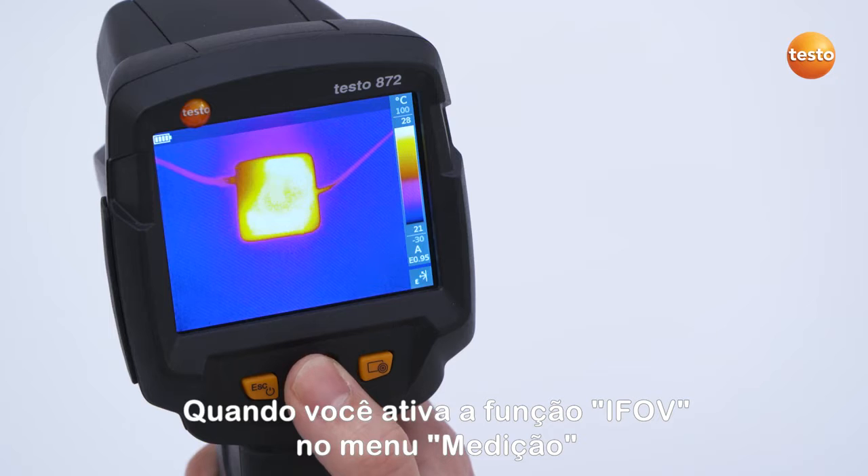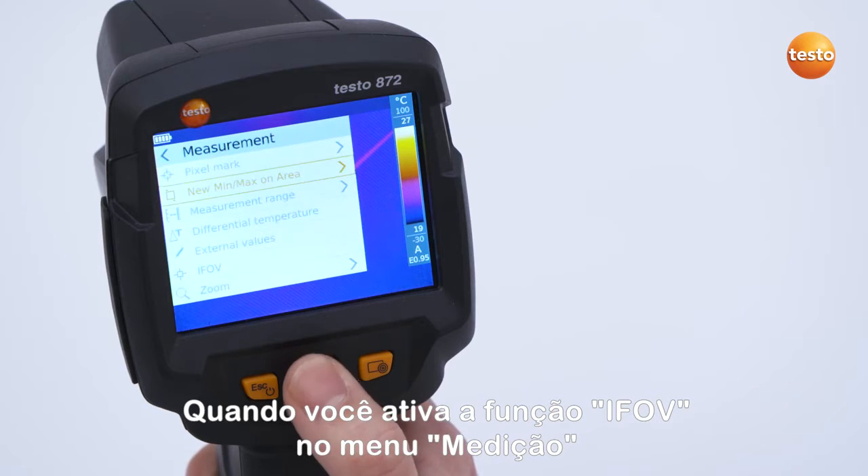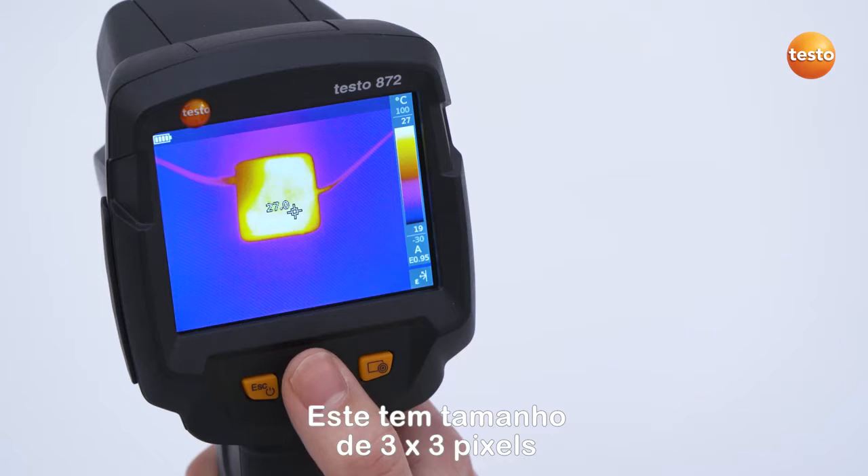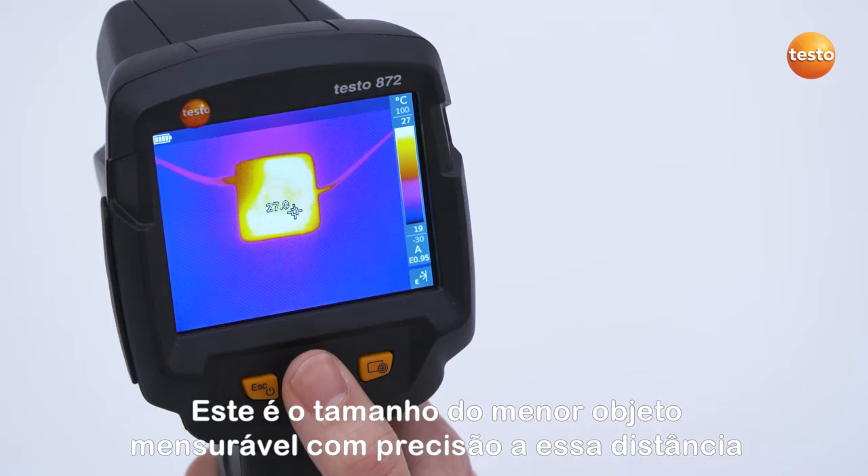When you activate the IFOV function in the menu Measurement, a square cursor appears in the infrared image. This has a size of 3 by 3 pixels — this is the size of the smallest accurately measurable object at this distance.